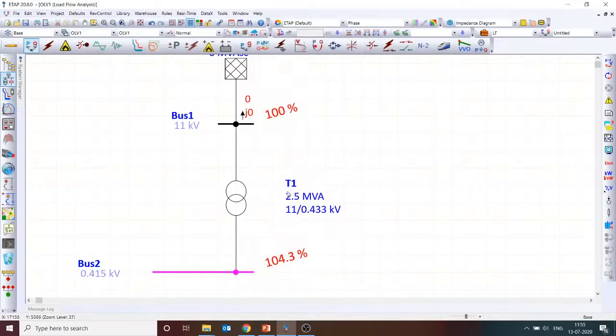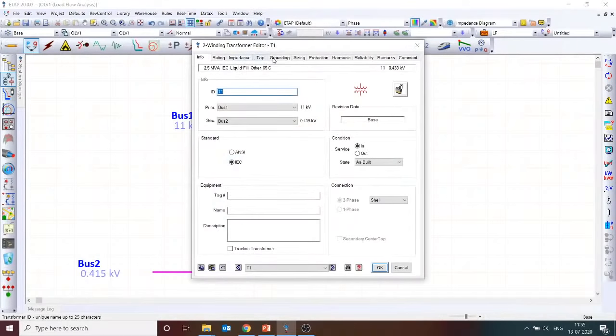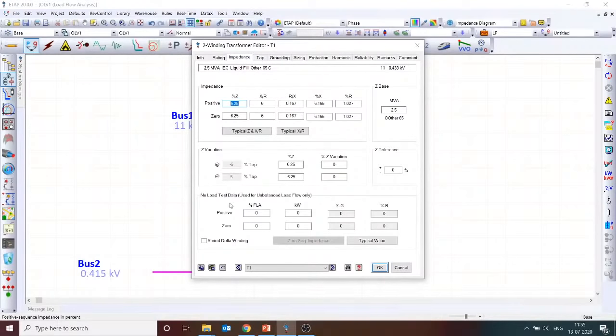So I have used a transformer of 11 by 0.433 kV, and I am connecting it to the 415 volt bus. So here, if you look, the voltage is slightly higher. If you plot with the units, I don't have any loads, so the power is 0 kilowatt, 0 kVAr. There should be a no load loss in the transformer, but that is not really accounted, because I have not given the data and that cannot be performed using balanced load flow either.